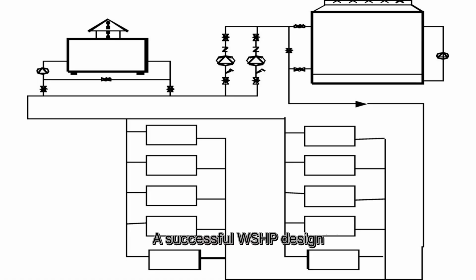A successful WSHP design depends on balancing airside and waterside components to deliver comfort, energy efficiency, and long-term reliability. Unlike centralized chilled water or DX systems, WSHPs operate as independent zone units connected by a common water loop that acts like a thermal battery. Each zone adds or removes heat as needed, while the central plant, consisting of cooling tower, boiler, and pumps, maintains loop temperature within the desired range.